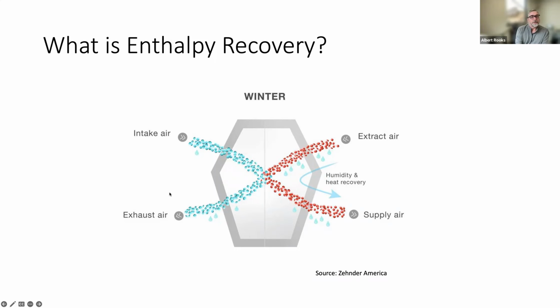Essentially what's going to happen is the air is going to transfer the energy across it, but it's also going to transfer the moisture across it like a Gore-Tex jacket. So extract air has maybe a little high level of humidity on it, and it's going to run across that through the heat exchanger. The intake air is going to be cold and dry. So that dry air is going to pick up the moisture across the membrane core and put it onto the supply air and bring it back inside the building.